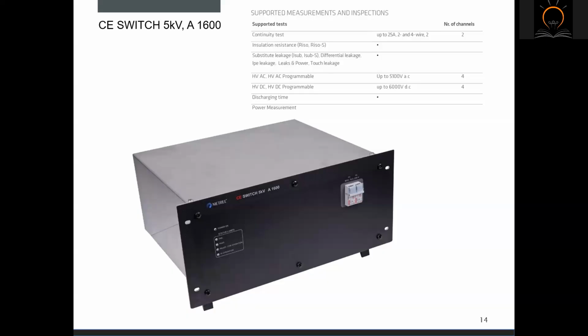A1600. The active CE switch 5 kV is an active multi-channel switch intended to run auto sequences or single tests on electrical equipment in combination with the master test instrument. Testing with high voltages up to 5.1 kV AC or 6 kV DC is supported. The operation of the CE switch is completely controlled by the master instrument. Therefore, no user intervention during the tests is needed.